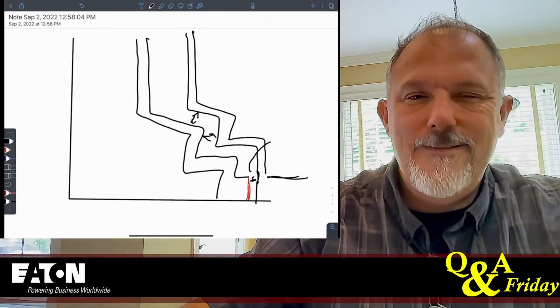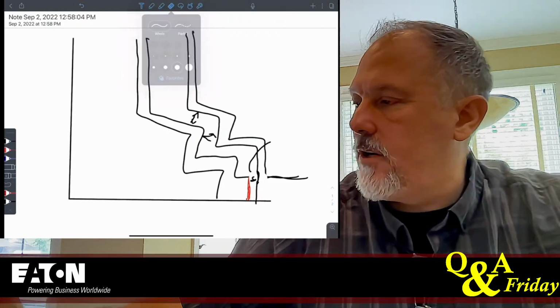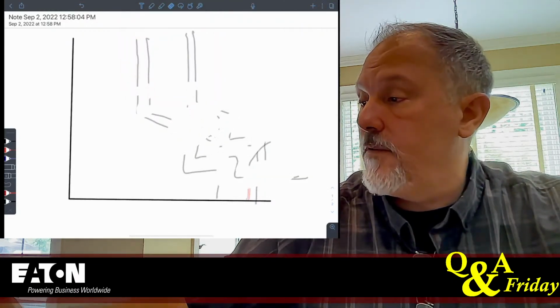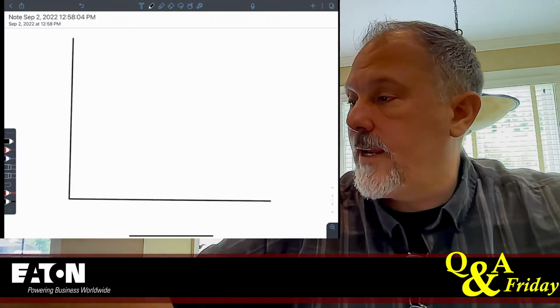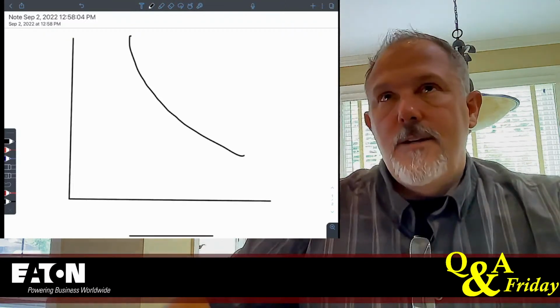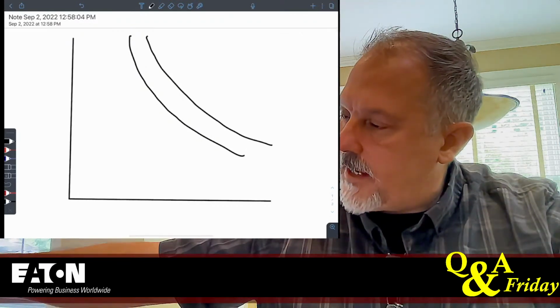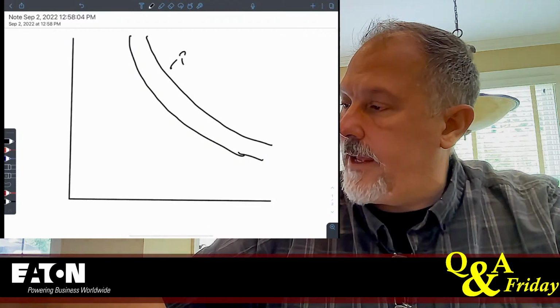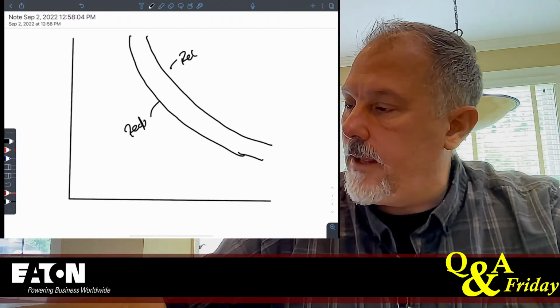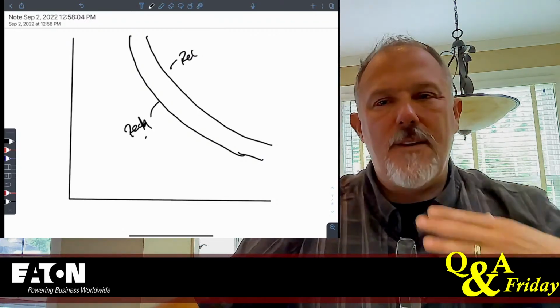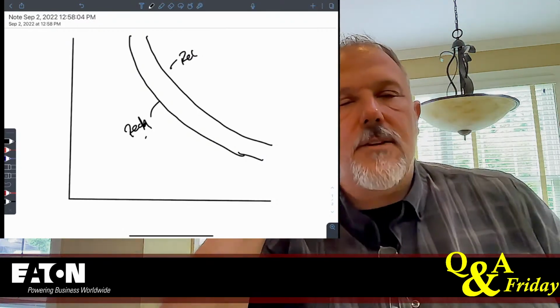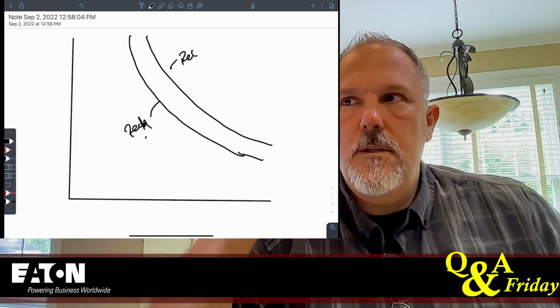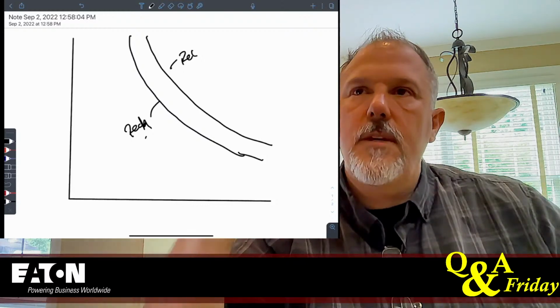So when you say milliseconds, you're talking time. And you specifically mentioned relays. So when I think of a relay curve, you're looking at something sort of like this. If it's a CO type of relay or whatnot, you might have something like this. And this is one relay, and this is another relay. It's not a band, because on relay curves I don't typically see bands. That's another good point. When we do relays, we never really see a band.